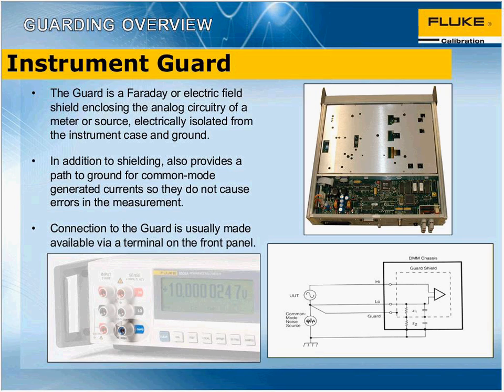Sometimes you also have a local or remote guard switch, a hardware switch on the front panel, or perhaps it's one of the controls you can operate through the user interface or remote programming of the instrument, where that terminal can be connected to and allow you to drive the guard from the instrument, from the outside world going inwards or the inside going outwards, depending whether it's a source or measuring device. That's a very complicated subject, and there is lots more information in the calibration book and some of the app notes that we really don't have time to talk about in great depth today, but just a little snapshot that it is something which is often misunderstood and misused.